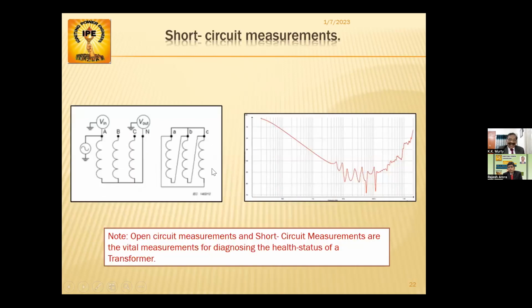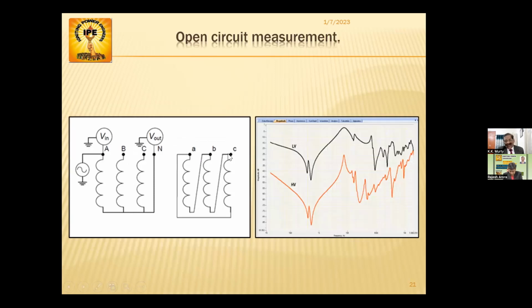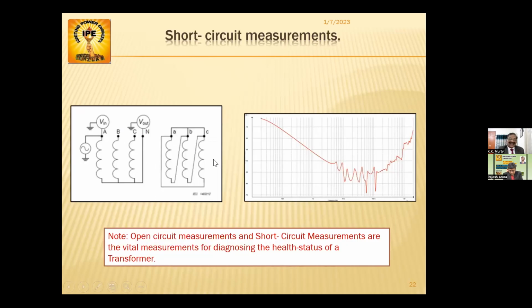And the next one is closed. This is the shorted, okay, the LV is shorted. So this is known as shorted LV. Here the connection is the same as the previous one, only this portion is shorted in the subsequent one. You can see this. Open circuit measurement and short circuit measurement are the vital measurements for diagnosing the health status of the transformer. This is the basic takeaway for anybody. There are 2 more connections, which I will show you in the further 2 stages.